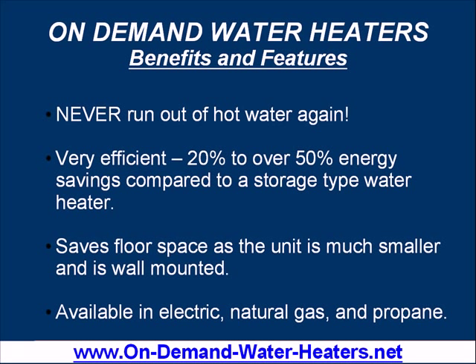As far as the floor space goes, there's significant savings there. This unit normally is wall mounted, and the large area that the water heater was on the floor before is now available for use for whatever else. So especially in areas where there's a tight furnace room or whatever, you gain the benefit of that extra space. And these are available in electric, natural gas, and propane.